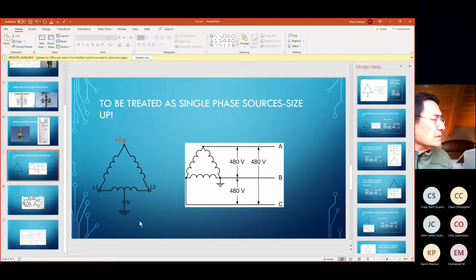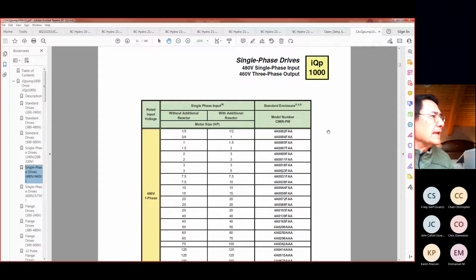So when you run into a stinger leg or a corner grounded delta, you must go to the single phase sizing that I showed you on the sizing of the drive. And in this case, we publish, and this will be on the documentation associated with this class that you can access on your team's membership, our single phase sizing, which is based on something other than rule of thumb. A lot of people still believe that you can use a rule of thumb in sizing VFDs. And during my career, which has spanned a relatively long period of time, that rule of thumb has changed. Early on, we used to say size up 1. Then it became double the VFD. Then it became triple the VFD. And then we said, no, we're not doing rule of thumb anymore because we're not addressing the issue with this general rule of thumb practice.